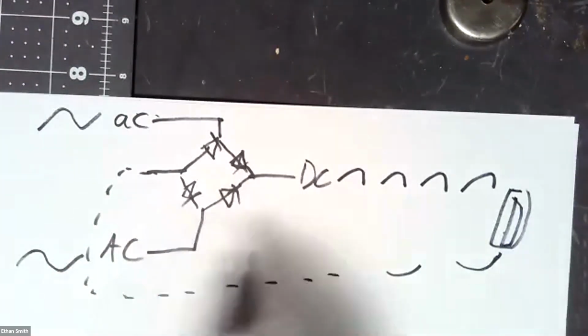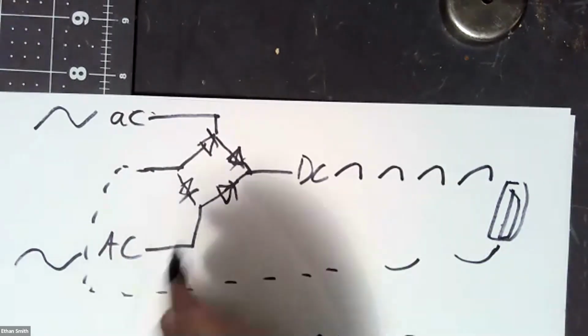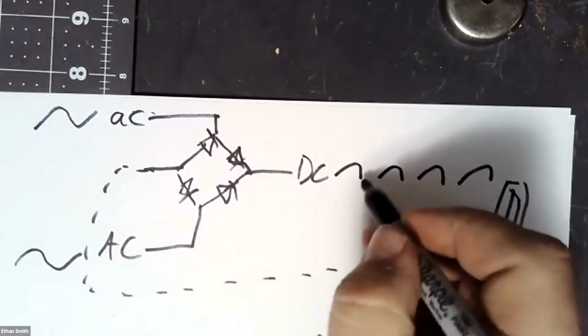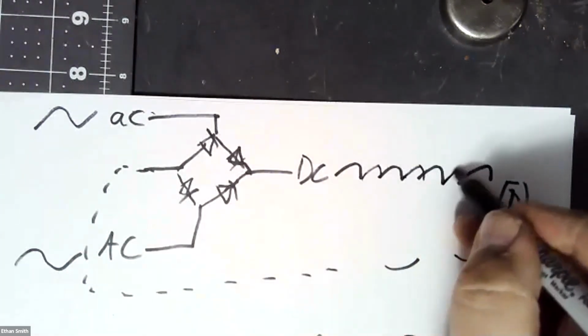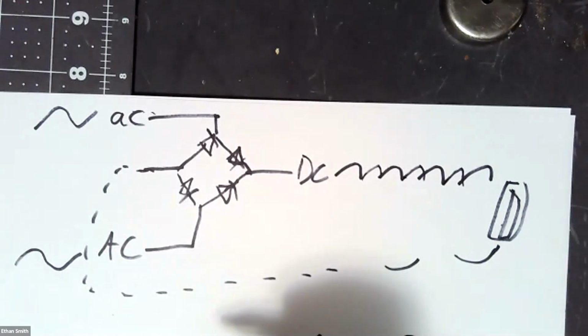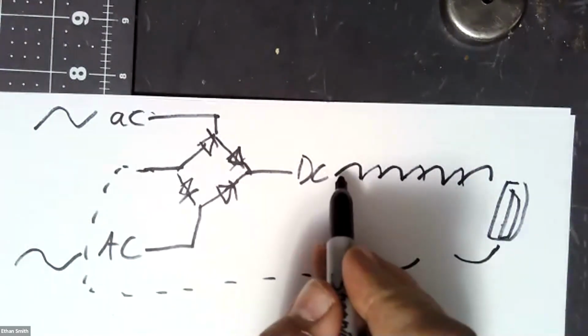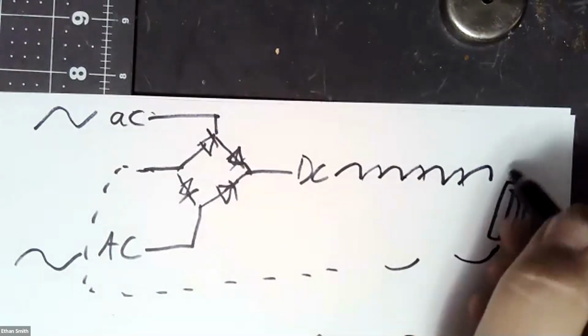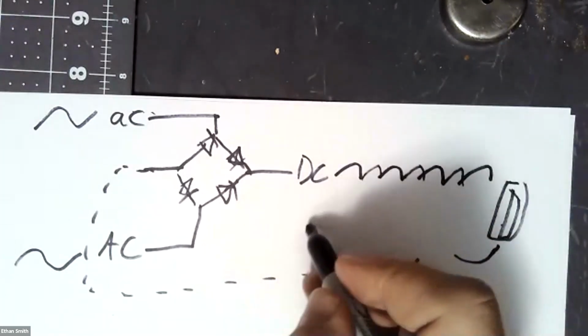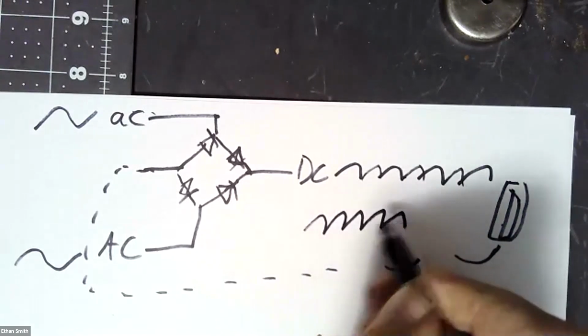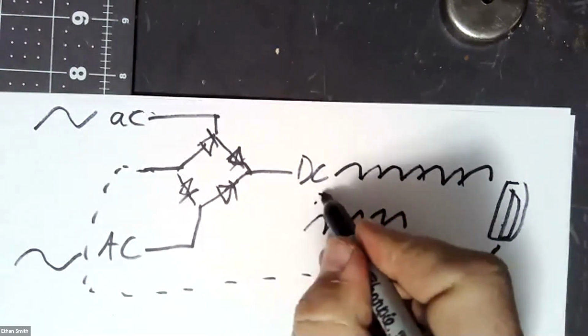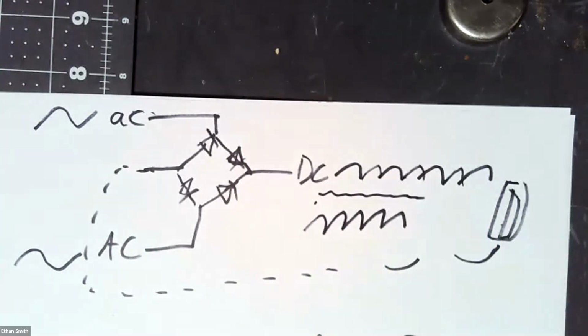All right. Thank you. So when we run a single phase circuit through this, it gives us a pulse DC. When we run a 230 volt or two phase system through this, we get a higher frequency of pulses. Okay. And then what Mitsubishi does is they take this higher frequency of pulses, they run it through what they call a smoothing circuit, so that instead of it being really dramatic like that, it comes out of the smoothing circuit kind of more like this. Okay. And then they use that to drive their variable speed stuff.